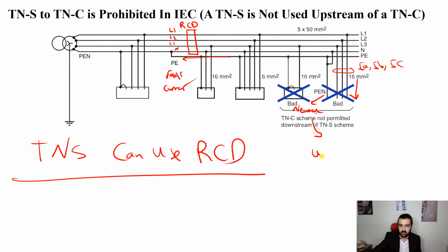So the unbalanced current will go like this. Let's call it IN, right? Getting back through the neutral. It wants to get all the way back to the neutral of the supply here. So what is it going to do? You can see that at this point here, part of it will say, hey, I'm going to get back through this neutral, I1, and another part will say, hey, no, I'm going to go through this protective earth.